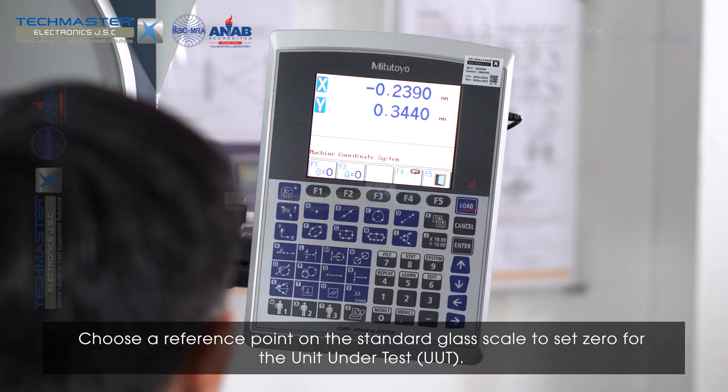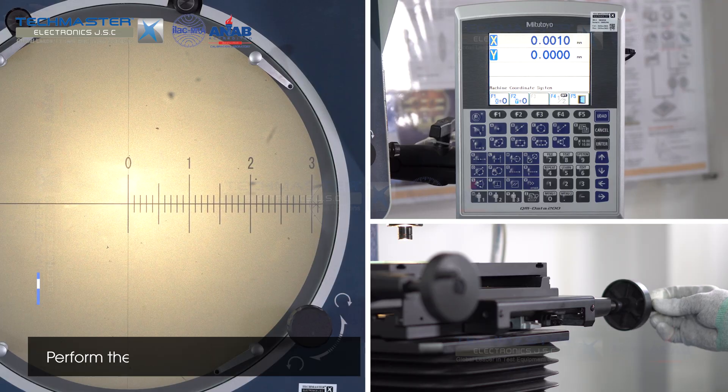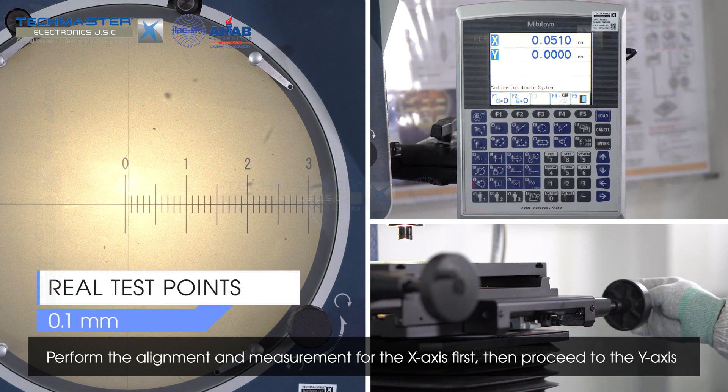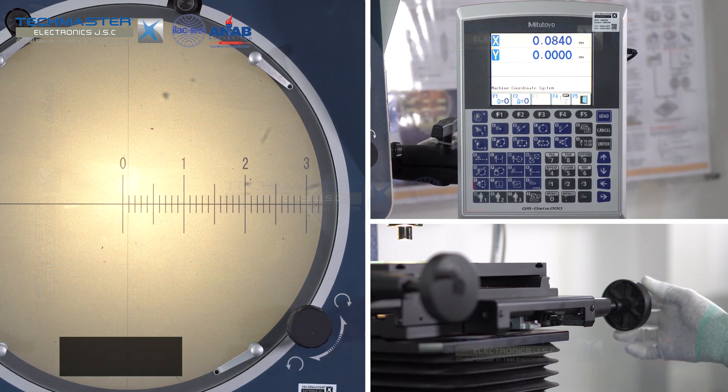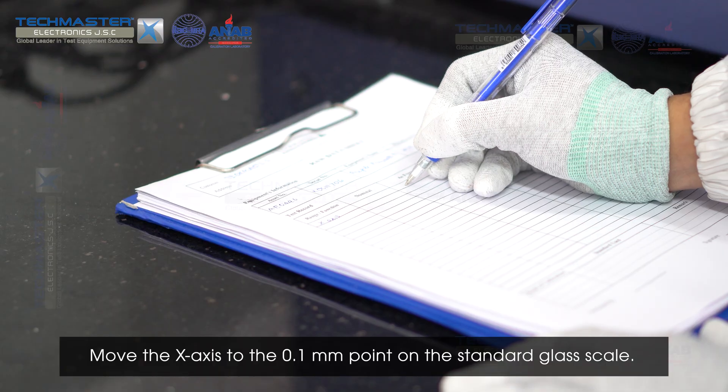Choose a reference point on the standard glass scale to set zero for the unit under test. Measurement for the x-axis first, then proceed to the y-axis. Move the x-axis to the 0.1 mm point on the standard glass scale. Record the displayed value on the unit under test. Continue the measurement according to the following inspection points.